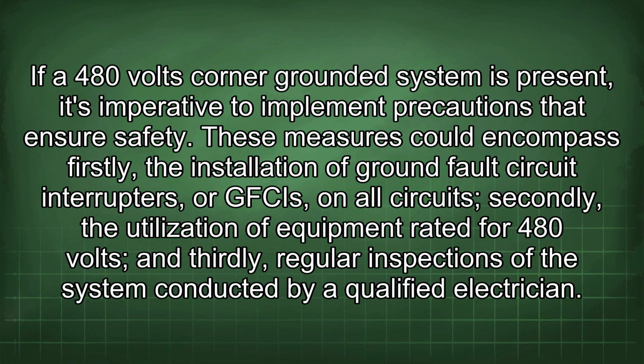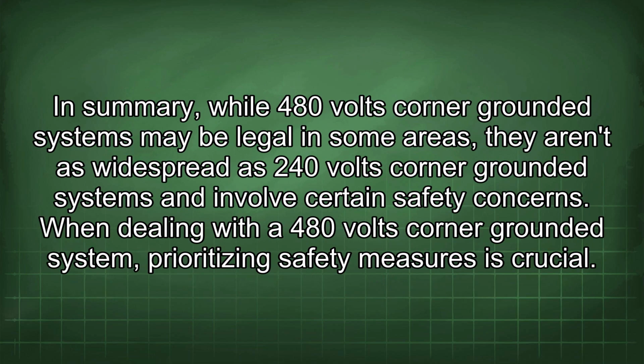If a 480 volts corner-grounded system is present, it's imperative to implement precautions that ensure safety. These measures could encompass, firstly, the installation of ground fault circuit interrupters, or GFCIs, on all circuits, secondly, the utilization of equipment rated for 480 volts, and thirdly, regular inspections of the system conducted by a qualified electrician. In summary, while 480 volts corner-grounded systems may be legal in some areas, they aren't as widespread as 240 volts corner-grounded systems and involve certain safety concerns. When dealing with a 480 volts corner-grounded system, prioritizing safety measures is crucial.